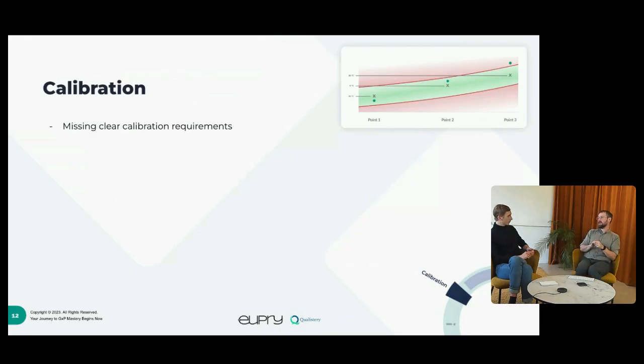What we often see in large organizations is that the requirements tend to be spread out or have non-coherence. There's a difference in different departments. And that's one of the things where it can be very hard to rationalize to customers, auditors or regulatory bodies why there are different requirements. The assessment should be the same, so why are the calibration requirements not the same?